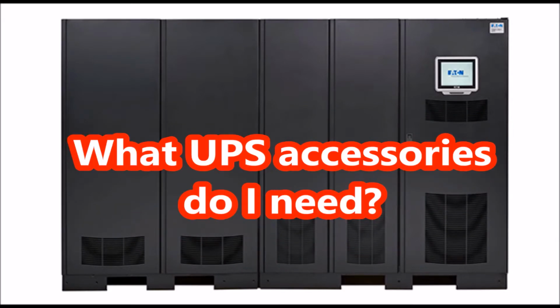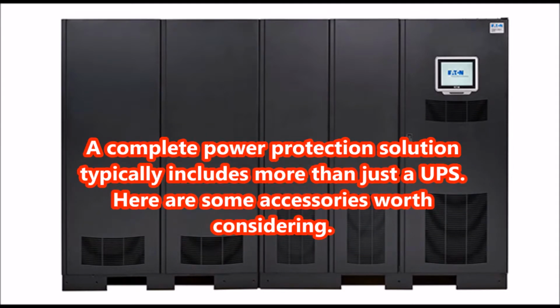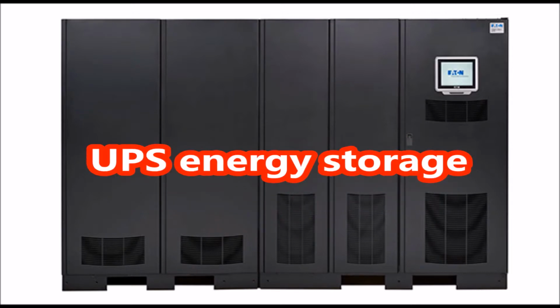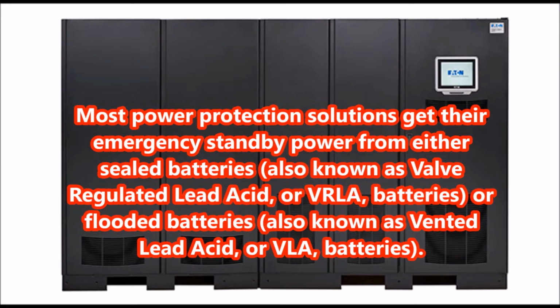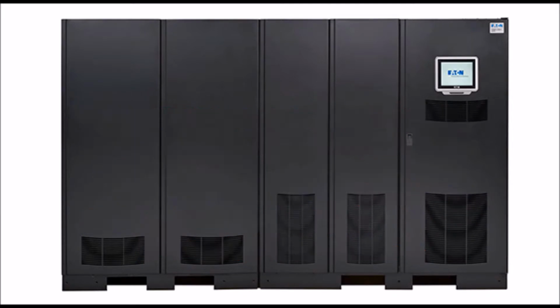What UPS accessories do I need? A complete power protection solution typically includes more than just a UPS. Here are some accessories worth considering. UPS energy storage. Most power protection solutions get their emergency standby power from either sealed batteries, also known as valve-regulated lead-acid, or VRLA, batteries, or flooded batteries, also known as vented lead-acid, or VLA, batteries.